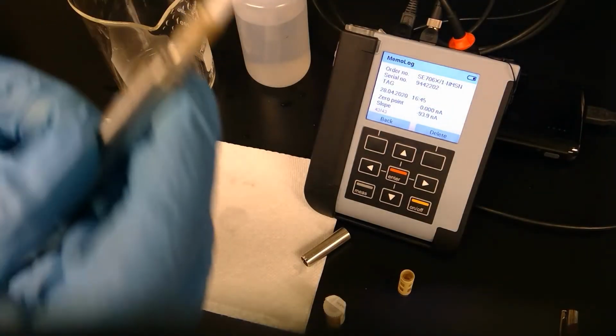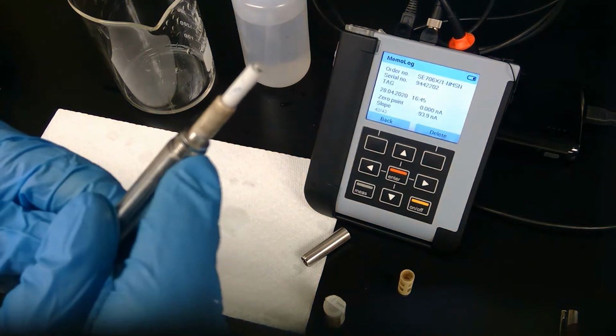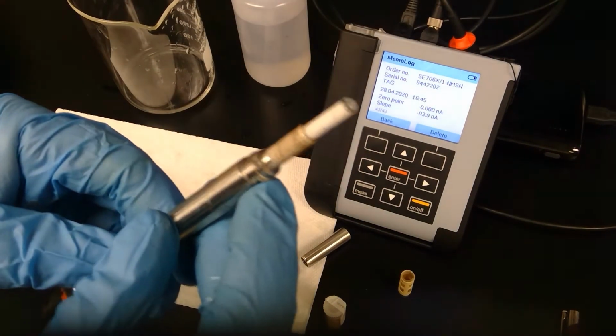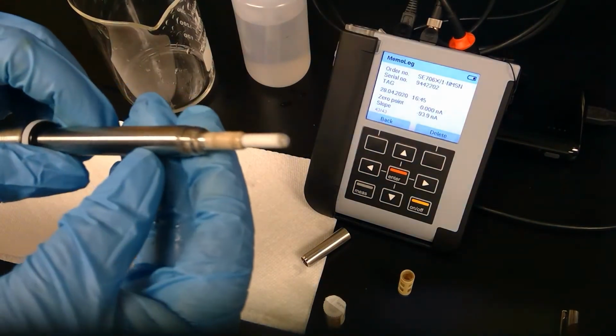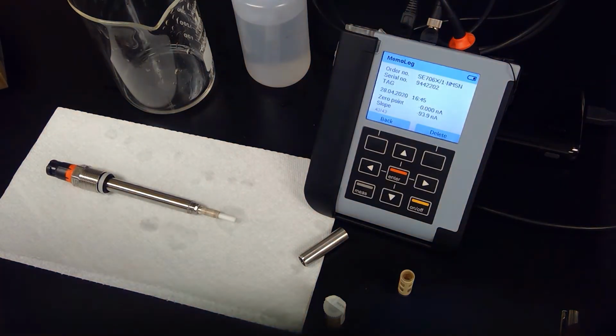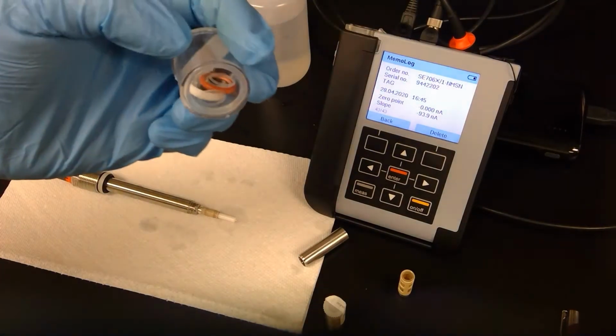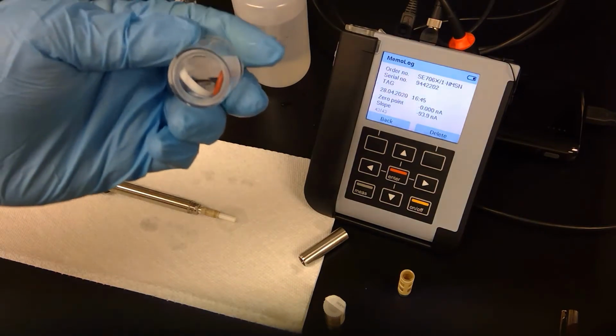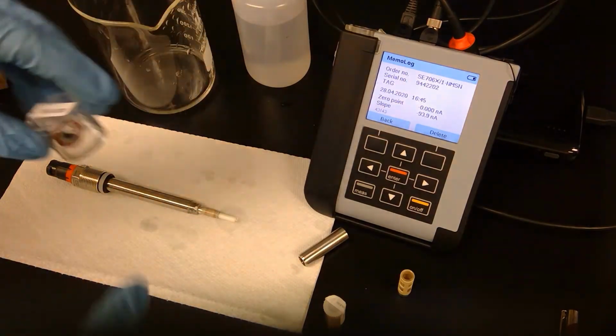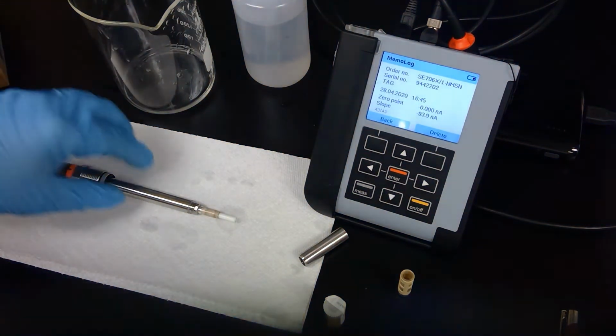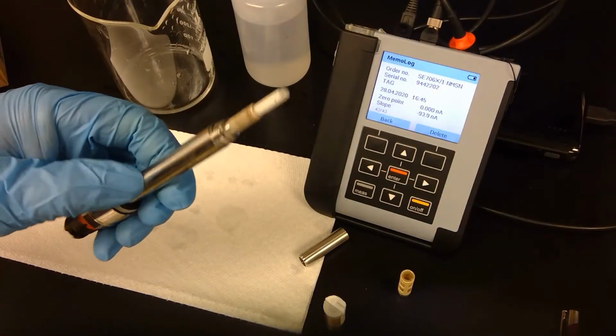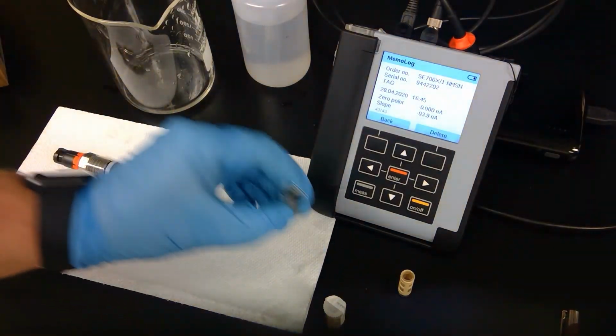So the O-ring that I'm talking about is right here. It's hard to see. And that O-ring, if it's damaged, you want to replace that. That's where this comes in handy. There's a variety of different O-rings for different types of probes, but the kit will contain one O-ring that you can use to replace the one on the sensor if you see that it's damaged. So just want to make sure you're aware of that.